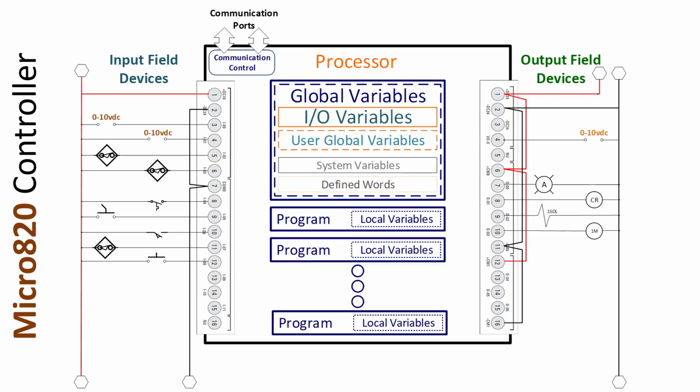Global I/O variables are determined by the embedded I/O count and type, and any plugin or expansion modules. The types are fixed because they are module-defined data types, which means the electronics has a fixed data structure. It's all pre-named and all predefined. So the I/O variables, you cannot edit those. You can change the size of that data table by adding or removing expansion or plugin modules.